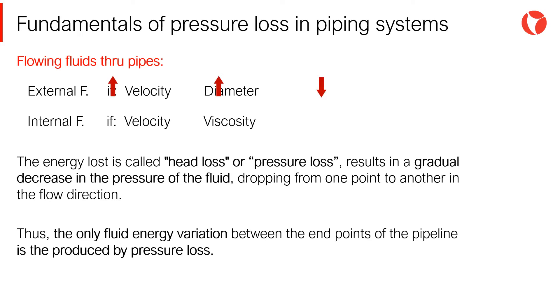External resistance will be greater the higher the fluid velocity and pipe wall roughness, and the smaller the pipe diameter. On the other hand, internal resistance will be greater the higher the fluid velocity and fluid viscosity. The energy used to overcome these resistances is called head loss or pressure loss, resulting in a gradual decrease in the pressure of the fluid, falling from one point to another in the direction of the fluid flow.